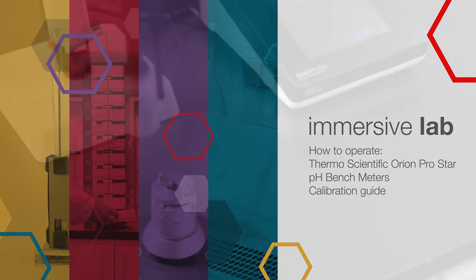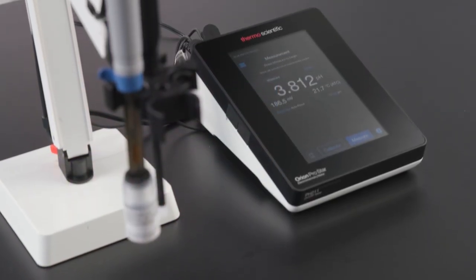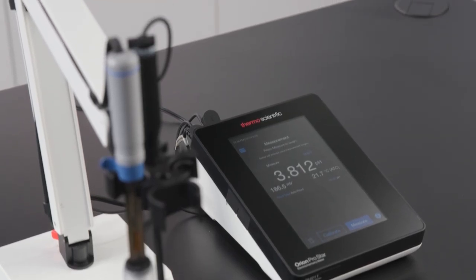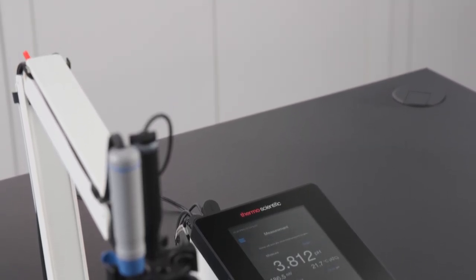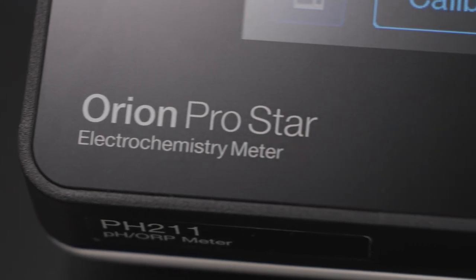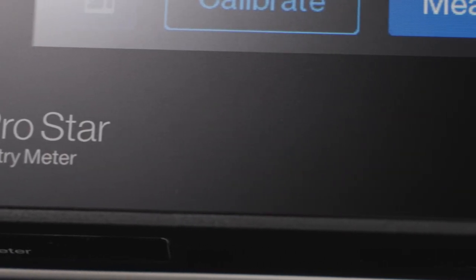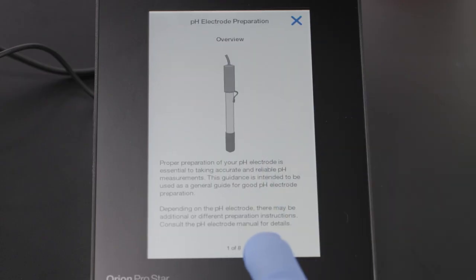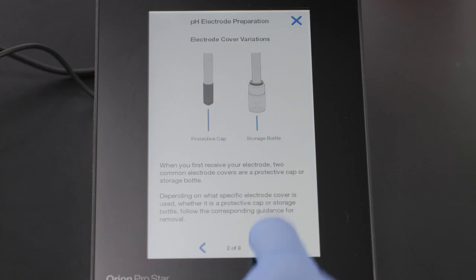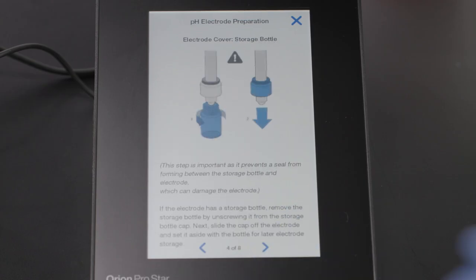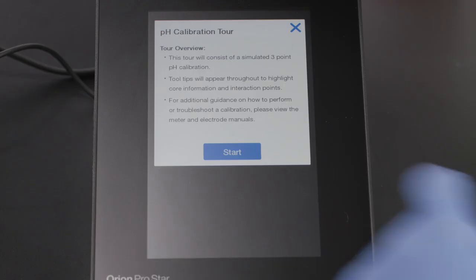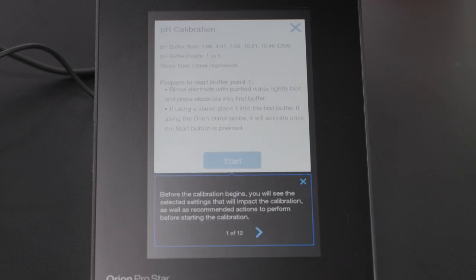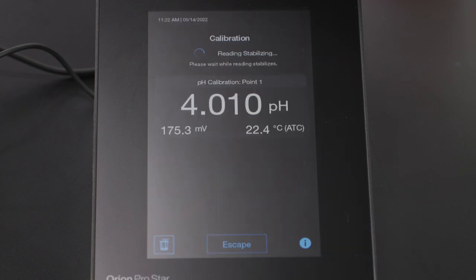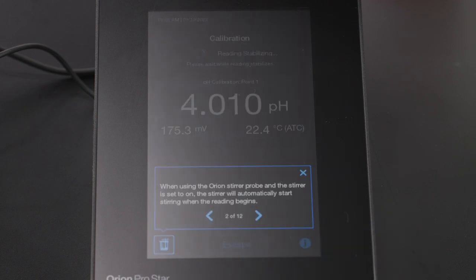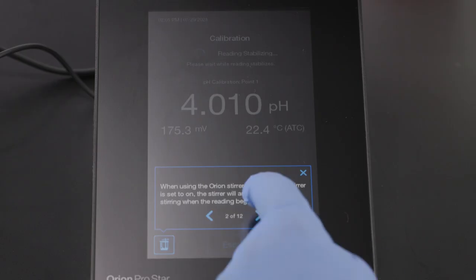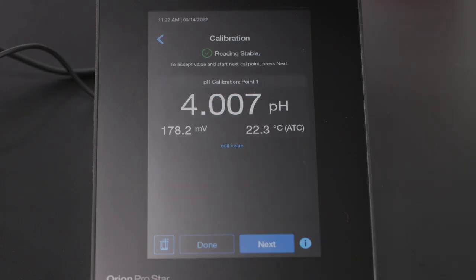In this video, we'll show you how to calibrate pH with a Thermo Orion ProStar pH bench meter kit. Before we start, we'll need to prepare the meter and the pH electrode. The Orion ProStar meter's on-screen guides for meter connections and pH electrode preparation can help. There's even a pH calibration tour that shows you each step of a 3-point calibration. These on-screen tools are great for first-time users and as refreshers for those who use the equipment infrequently.